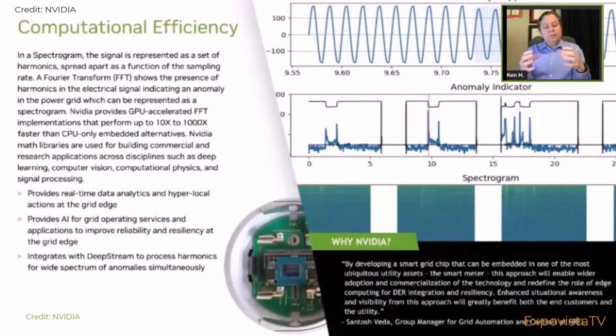We can actually begin to use AI to identify and categorize the actual type of event that's happening within the power signal. We always draw these power signals as really smooth lines, but if you look deeper, they're not quite that clean. So what we've chosen to do is look deeper into the harmonics, that noise within the line, and transform that noise, those harmonics, at maybe up to 60,000 points per minute, and look at the signature or characteristics of the event happening, not only at the waveform level, but at the harmonics level.